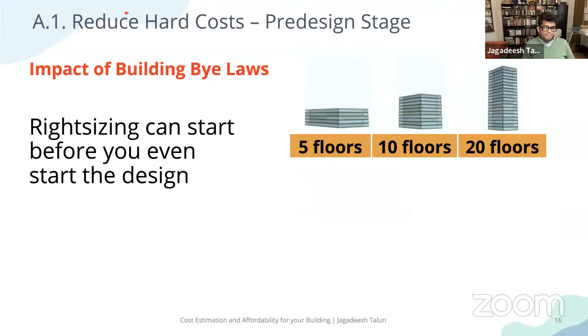All 3 buildings have the same specifications, occupancy, and scheduling. Because of that, the lighting and equipment energy consumption may be the same between a 5-floor building and a 20-floor building. But if you look at the air conditioning energy usage, it has reduced substantially. You may think this is just an OPEX measure, but because the heat load is reducing, your chiller plant size is also reducing. Instead of 465 tons, you now only need to buy 345 tons, which means you've saved money, and you're also consuming a lesser amount of lift energy, because you need fewer lifts in a low-rise building compared to a high-rise building.